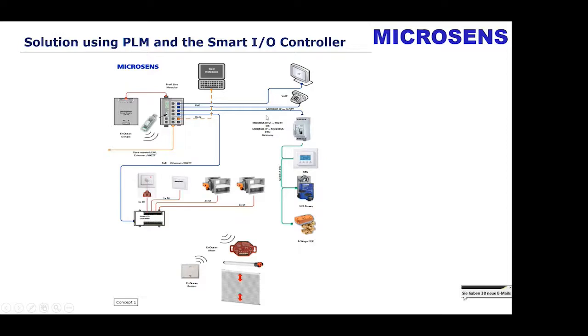This is very important. All our devices support MQTT as a standard communication protocol for the data transfer from the field to the switch, so that you can use these devices also to connect directly to a cloud. In this case, we also have conventional gateways available in the market, for example from Modbus RTU to MQTT. This allows conventional Modbus devices connected over this gateway to communicate via MQTT to our switch.